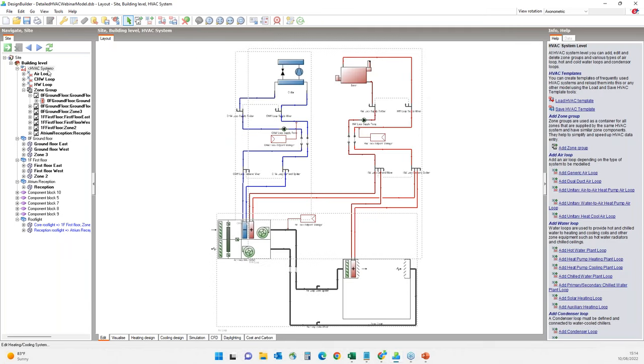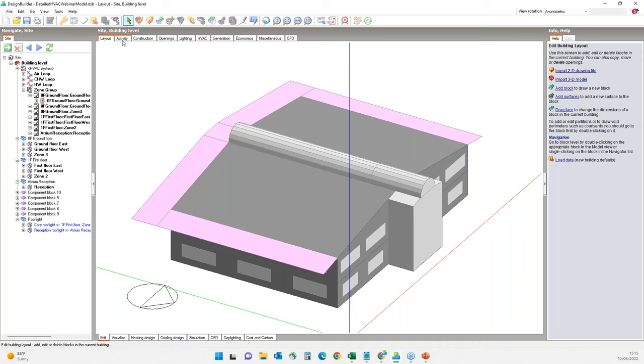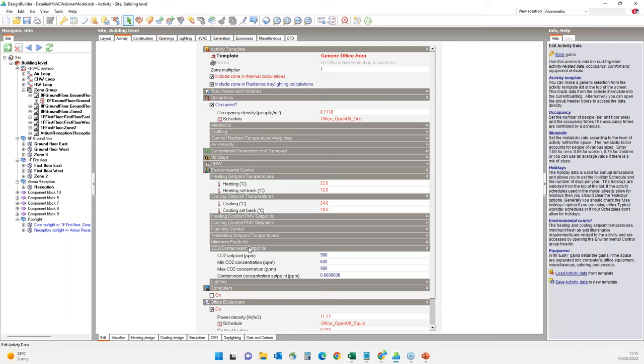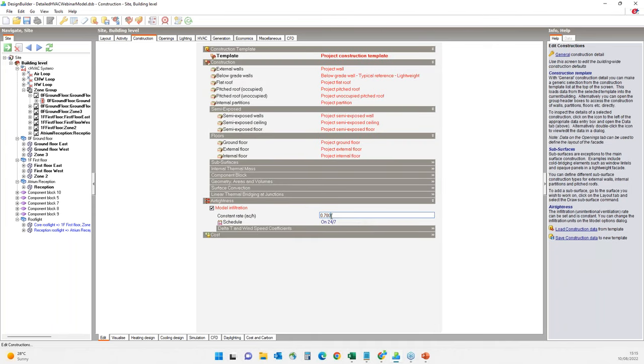I'll briefly review the key model data tabs before running the simulation. On the activity tab, amongst the environmental control options, we have the CO2 setpoint — this will be our demand control ventilation setpoint, and the system will keep indoor CO2 levels at 900 ppm. On the constructions tab, the default infiltration levels are quite high at 0.7, so I'll change it to 0.1 air changes per hour.